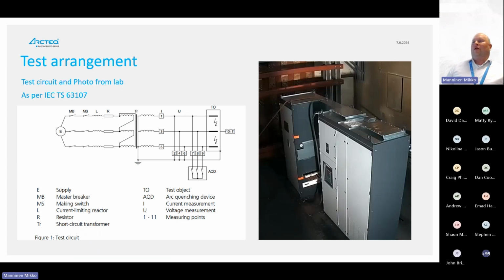Here is an example. Also earlier in some of the presentations, new standards were mentioned, some parts of the standards. Typically, IEEE 1584 and 1584.1 have been used as the de facto standard. NFPA 70E has also been used as a de facto standard combined with this IEEE. And from NFPA 70E, you get the calorie ratings for the PPE levels, but there are a lot of other global standards. IEC is seen very often as a European standard, but it is actually an international standard.